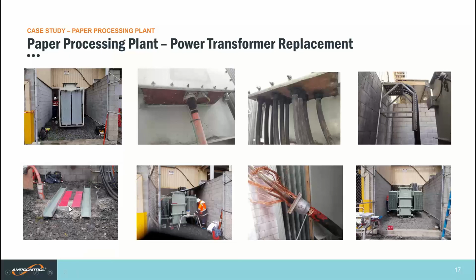First photo on the bottom left is some supports, as the existing concrete pad for the older transformer was not quite large enough to take the new footprint. So some support beams were used, and under those support beams, you can see the pink pads there. They were anti-vibration pads. The new transformer, while being lower than the original, was a little bit wider due to the cooling fins on it.